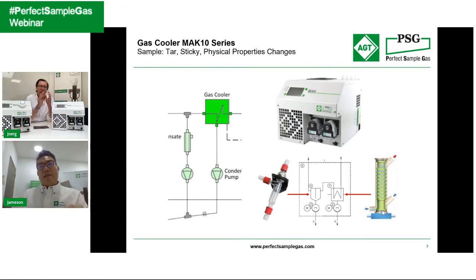So having this setup, let me get that straight. This really fascinates me still today. We have the hot gas sampling probe, maybe 180 degrees C holding temperature. In previous webinars we discussed why it's so important to have a temperature of 180 degrees C, as an example, and we agreed this is the acid dew point, which requires a higher temperature. Then the gas flows through the heated sample line and arrives at the cooler.